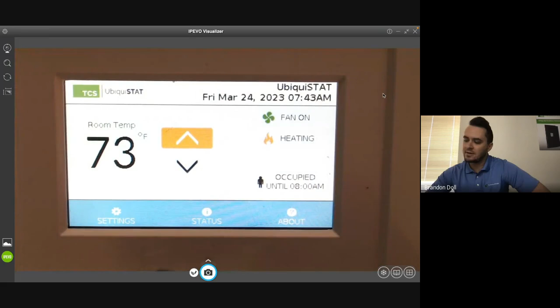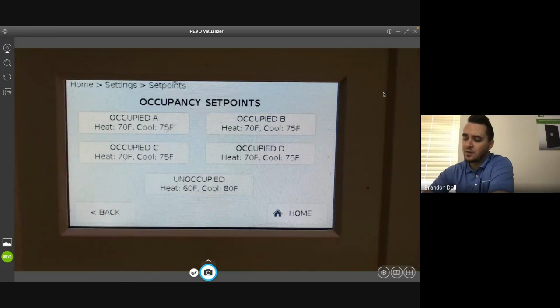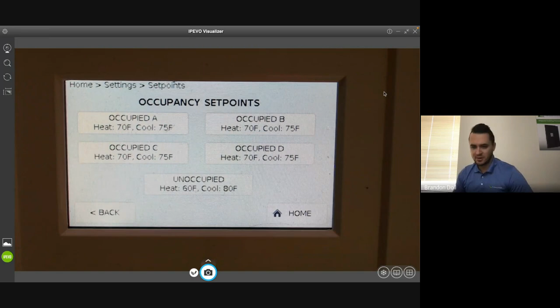Now, getting a little bit further into this, I'm going to go into the settings page. A lot of this was covered in the Quick Start Wizard, so if you ever want to change that, you can just go in here and change it. You don't have to reset the whole thing. So fan mode, system mode, that's stuff we covered in the Quick Start Wizard. Now set points: you can have up to four occupied set points and one unoccupied set point. You could always use an occupied as a different unoccupied set point if you just want to put it in the schedule; you can manipulate it how you want to. But there is a 1 degree dead band, so you're never going to be running heat and cool at the same time.